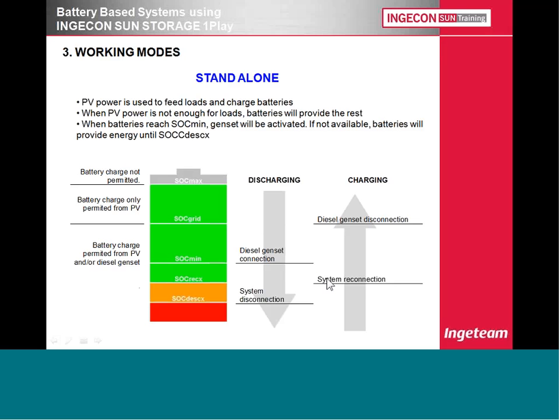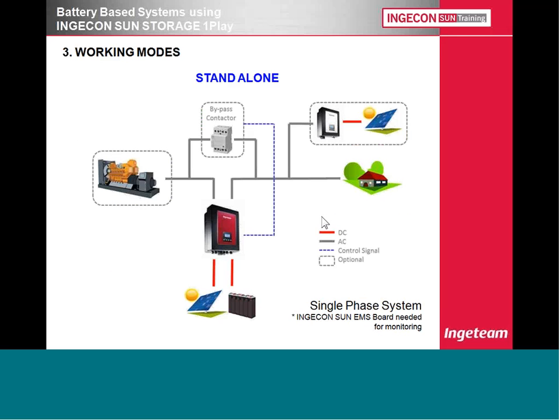That's very positive. The other thing you can do is, if you have too much PV power, and imagine that you have charged your batteries fully. You have reached the maximum state of charge, and you are consuming that power from PV because you have too much. Imagine that you have even more than what you need. In that case, there are two things you can do. You can limit your inverter not to produce that much, or you can even feed the grid. Okay, there are locations where that's all right. There are countries where feeding the grid is accepted. It's not the case for Spain, for example. I don't know how it is in South Africa, but you could either limit your inverter or you can allow grid injection. Okay.